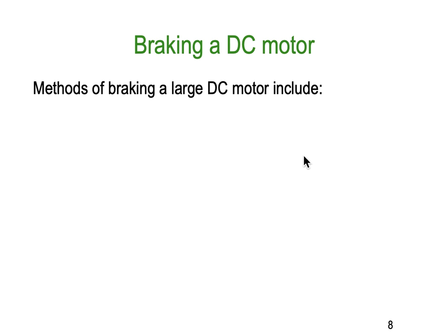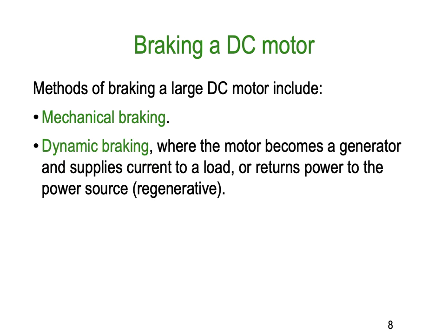Once our motor is up and started, what about slowing it down? We can use mechanical braking — a physical brake with a big drum and brake shoes. We can use dynamic braking, where the motor becomes a generator and supplies current to a load, or returns power back to the source — and we give that the special name regenerative braking. Dynamic braking has two components: generating back into load resistors, or regenerating back into the supply.